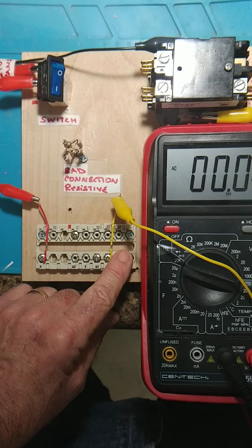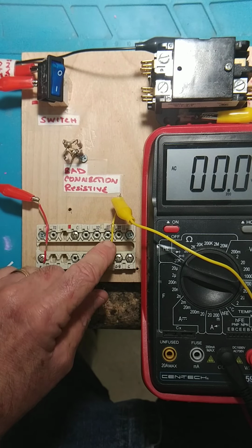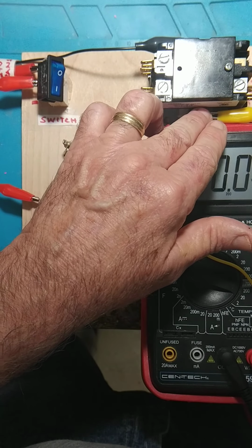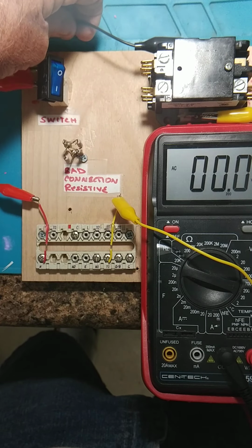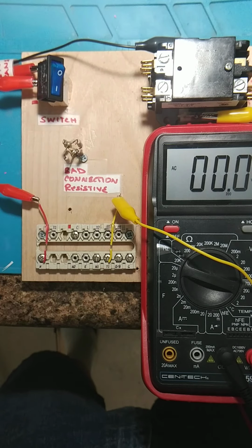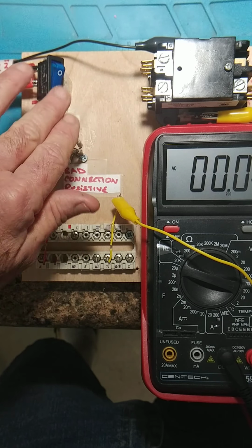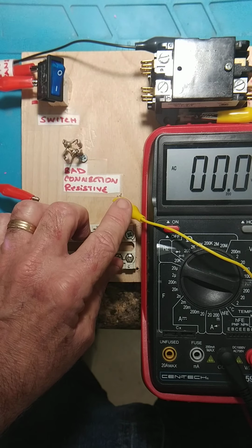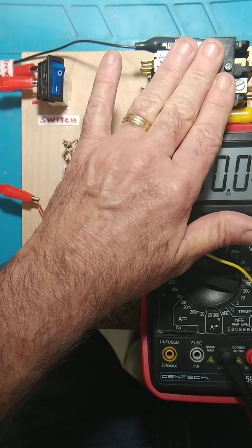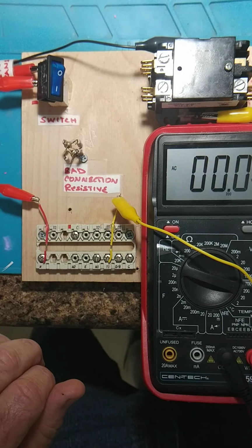Coming out of the other side of my thermostat, I have Y, which is coming over, and it is connecting to the other side of my 24 volt coil or my compressor contactor. So common is always feeding, which is typical, and R is going through a float switch to R on my thermostat, to Y, which is connected to my compressor contactor. This contactor could be in a package unit, or this could be a remote in the condensing unit. That's remote.